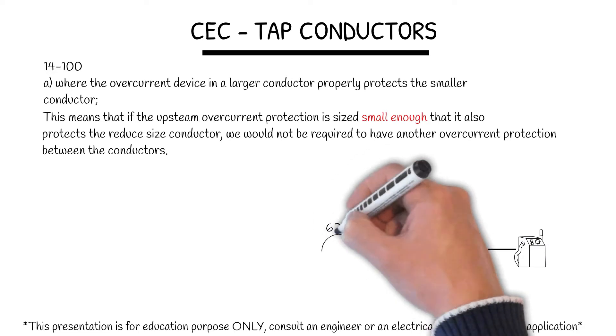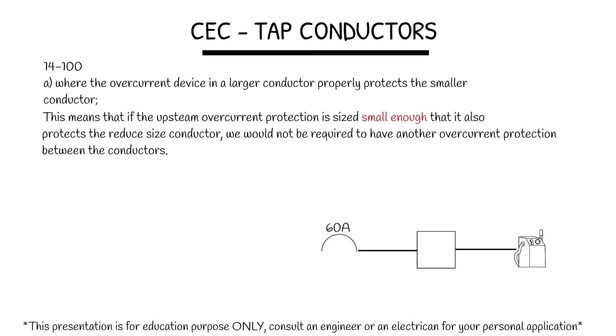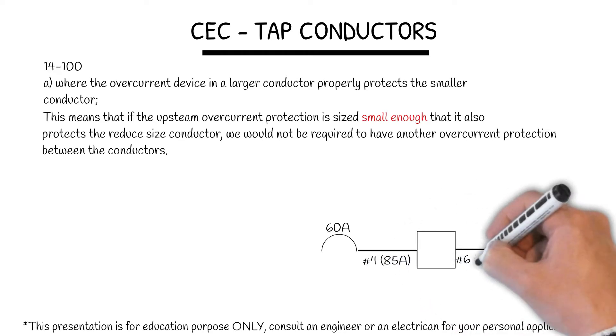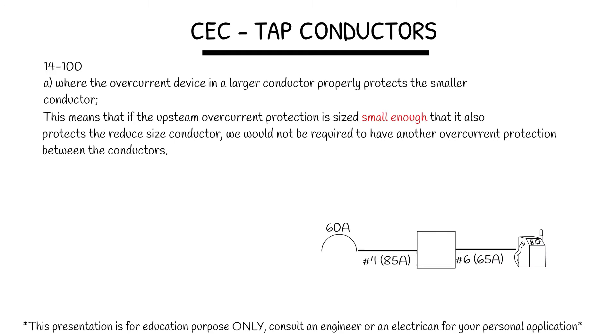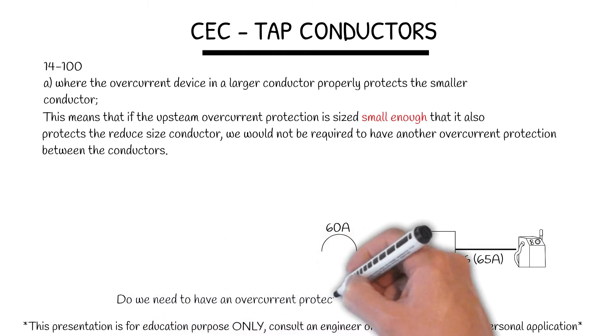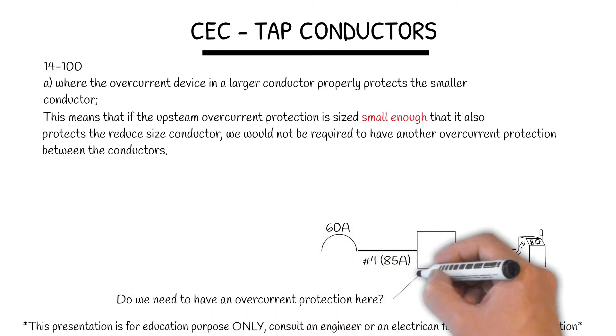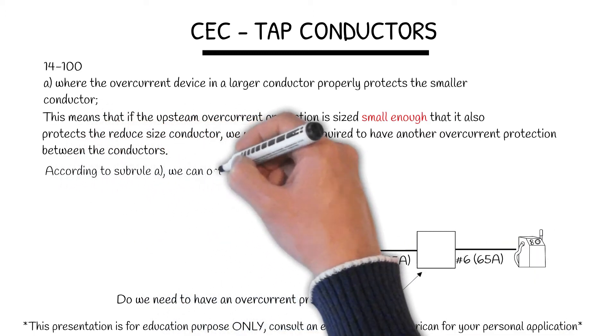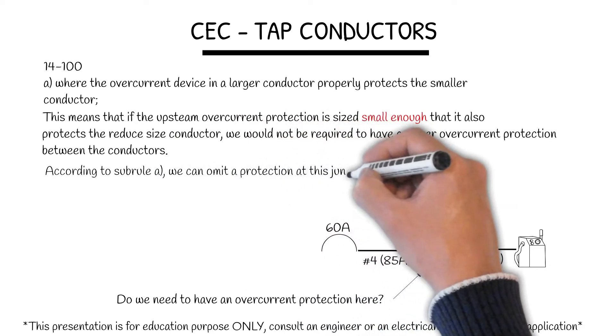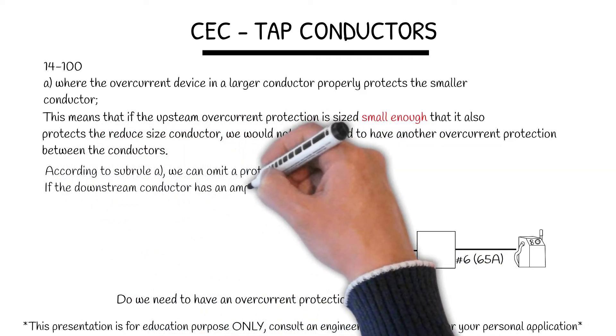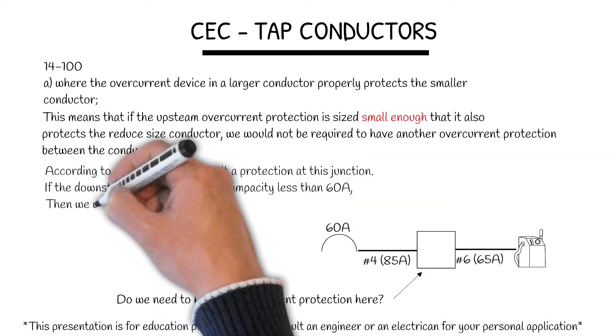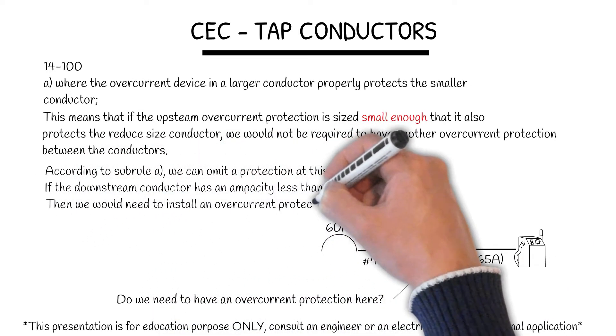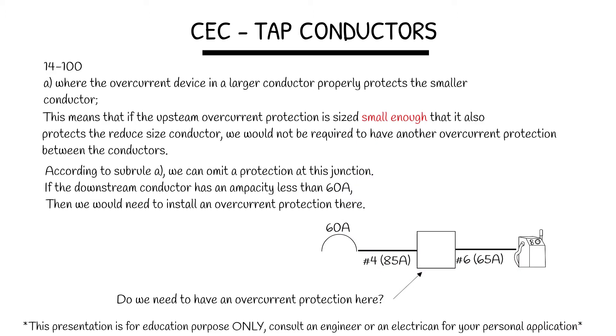Our overcurrent will be 60 amps. The main feeder will be number 4, good for 85 amps. And our load conductor will be number 6, good for 65 amps. Do we need to have an overcurrent protection here? According to Subrule A, we can omit the protection at this junction. If the downstream conductor has an ampacity less than 60 amps, then we would need to install an overcurrent protection there. So in this case, we are OK.